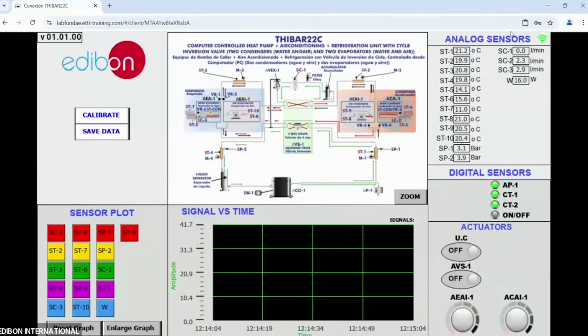Okay. On the right side, on the bottom, we have the actuators, okay, with which you can control different items of the system. For example, you see the compressor, AVS-1 is the four-way valve, and these two are the fans for the evaporator or condenser, depending on what you're using, okay? Also, at the bottom in the middle of the SCADA software, we have the graph. It's very easy, very visual, because you can choose all the values that you want to see, okay? And depending on how you act with the actuators, these values are going to change in real time, okay? For example, we're going to use the flow meter of the compressor, okay? I mean the flow meter of the refrigerant, that is SC1.